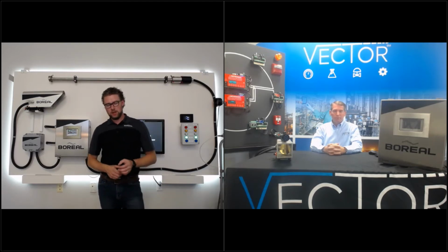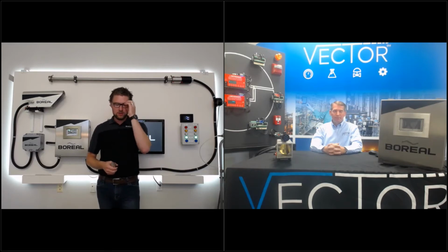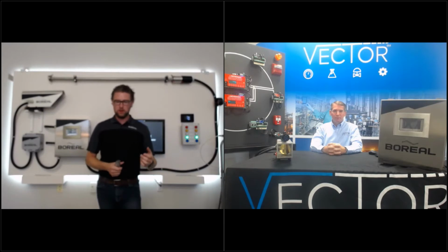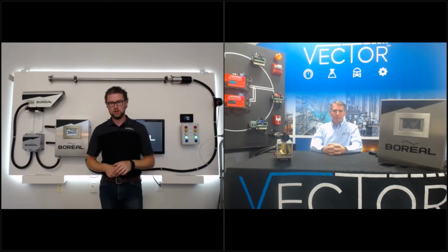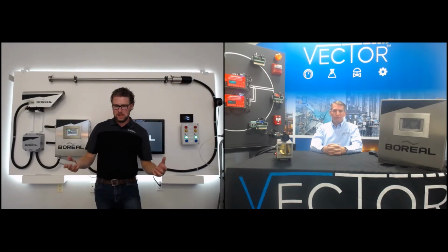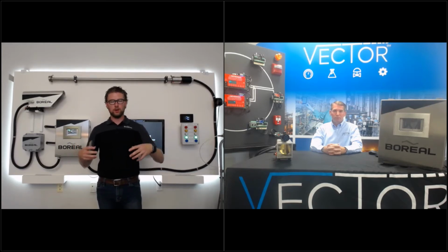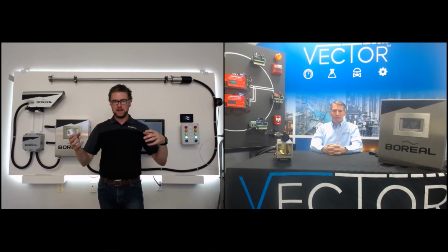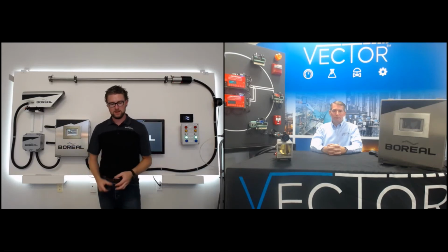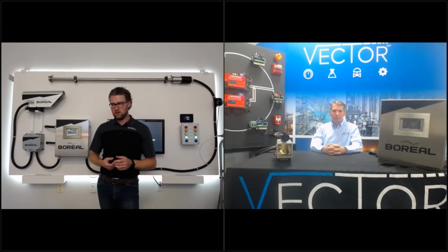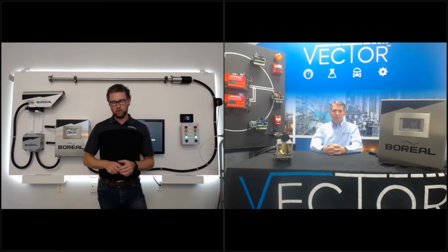Thanks, Chad. Yeah, Chad brings up a very good point that with this particular product, the main driver for this to be installed within industrial facilities or industrial leak detection applications is safety. The purpose is, is there a large enough leak present to warn, whether it's toxic or combustible gases, to allow enough time for your safety system to intervene to protect people and assets? But there are a number of other uses for this particular equipment that you're not going to get out of your other traditional simple fixed point gas detectors.